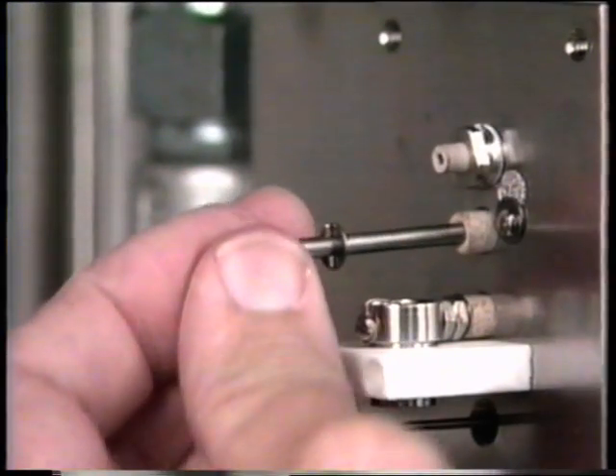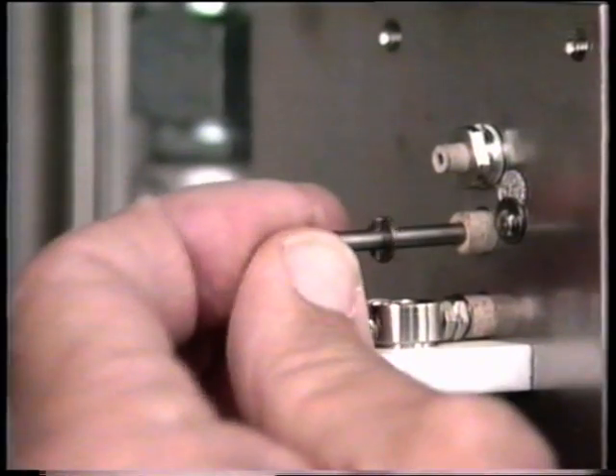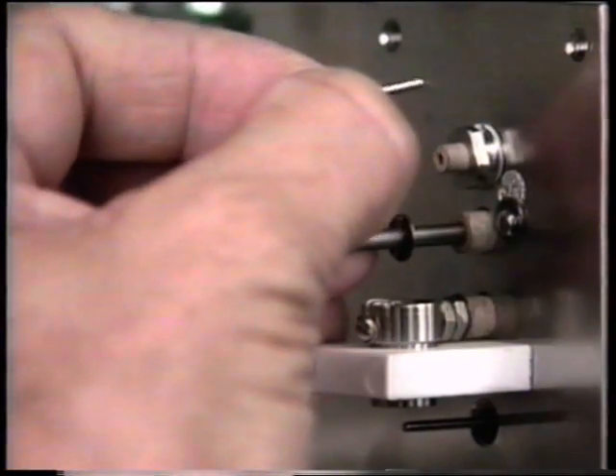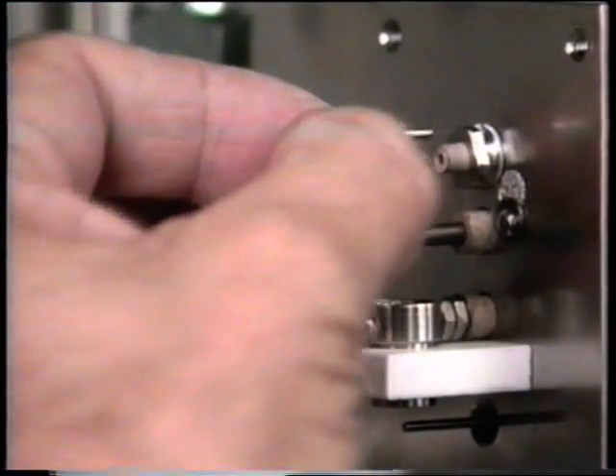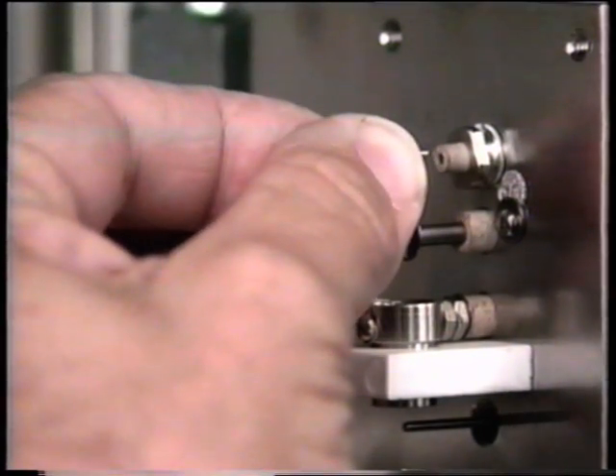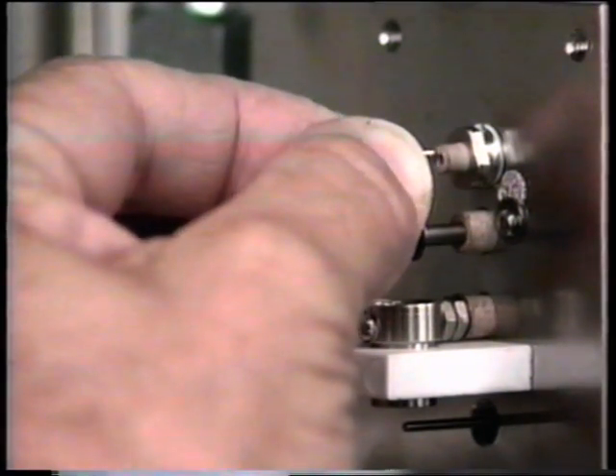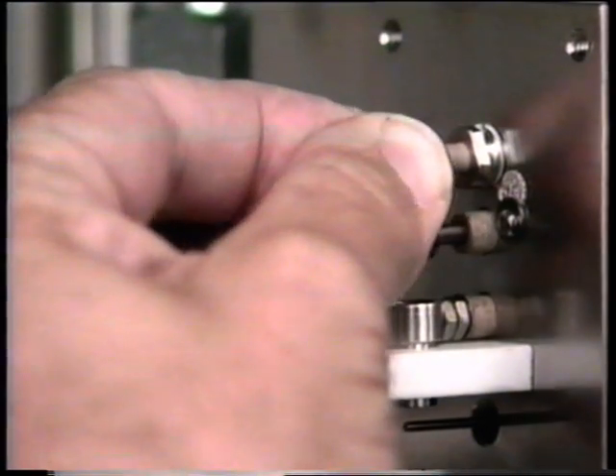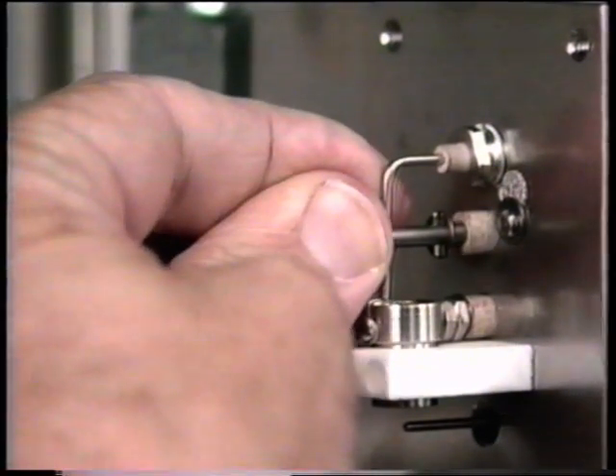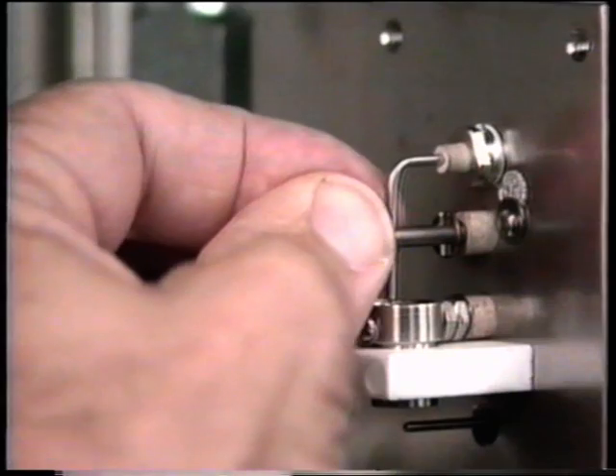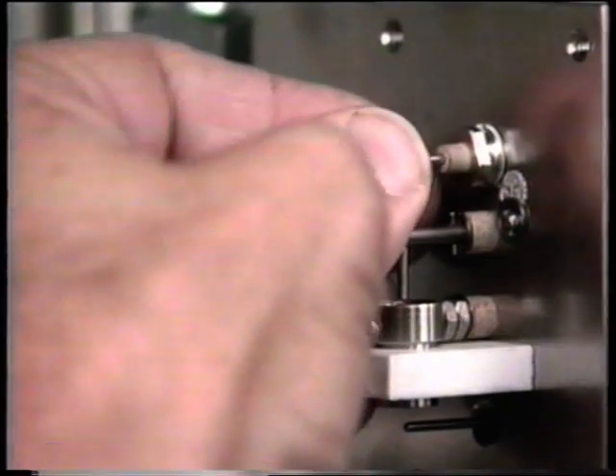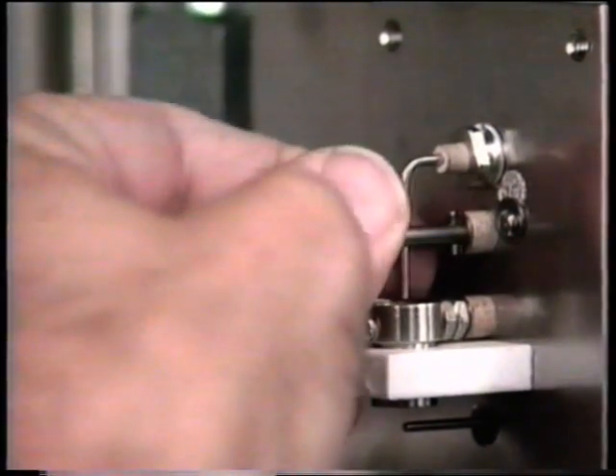Insert the bias ignite electrode partway into its insulator. Insert the long end of the burner tip through the hole in the electrode. Align the short end of the burner tip with the hole in the end of the ferrule. Push the burner tip and the bias ignite electrode toward the body until the long end of the burner tip is centered over the collector and the short end is pushed into the ferrule.